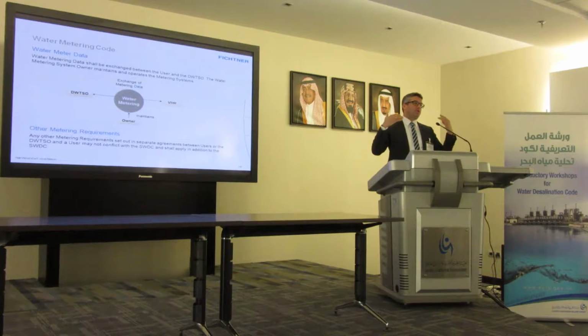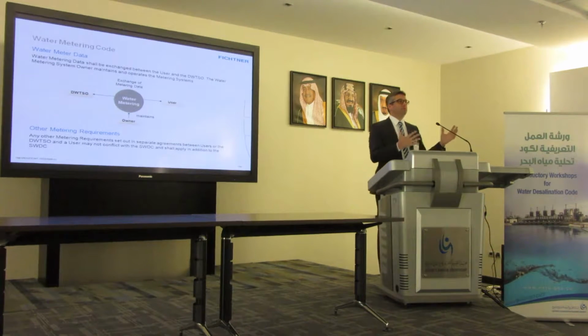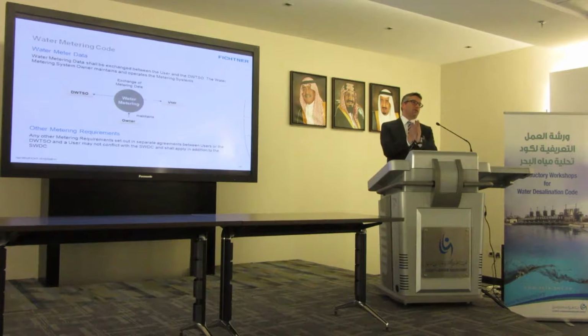If you recall, the setup was that between the production and the transmission operates the main meter, while the production operates the backup meter. From both ends, the data shall be exchanged between the parties in order to give both parties the possibility to double check the data. And most likely these data are exchanged in real time through appropriate protocols of the SCADA systems.